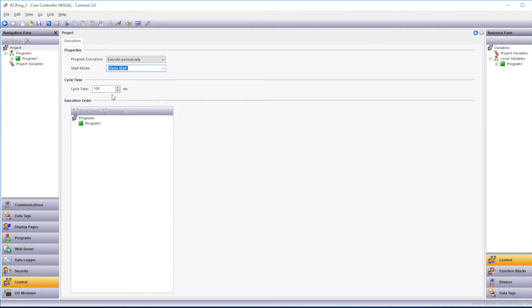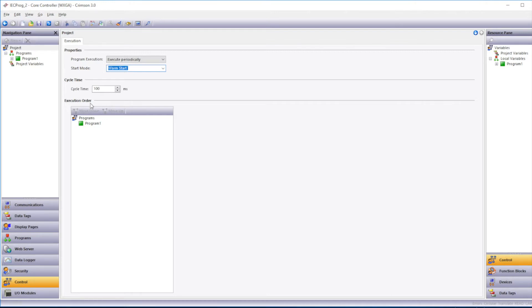The Cycle Time is the periodic value in which the program will run. We can set that to a different variable. 100 milliseconds is the fastest time that you can set. The Execution Order window down here will allow you to control which program, if you have multiple programs, will run first. So you can set the order in which they execute.